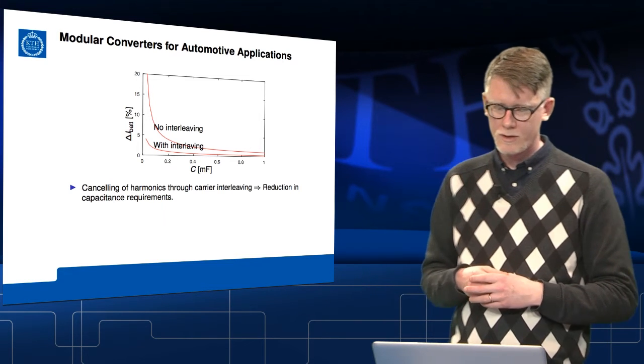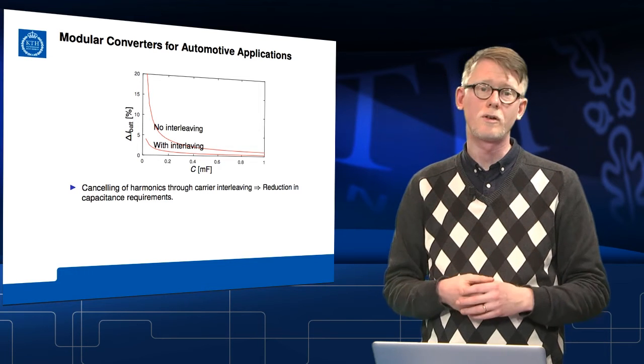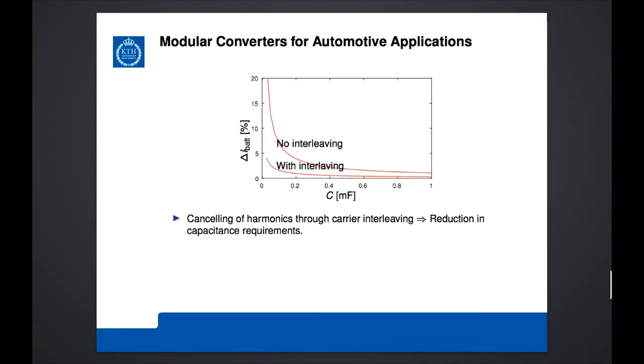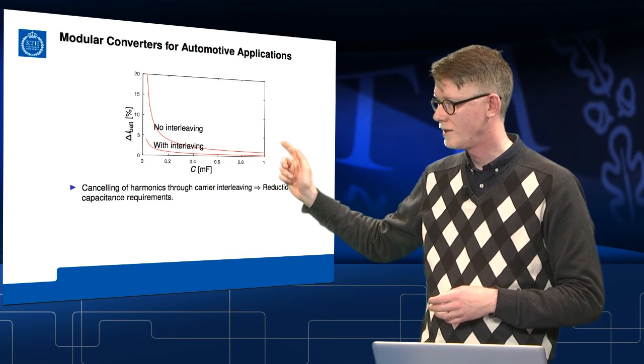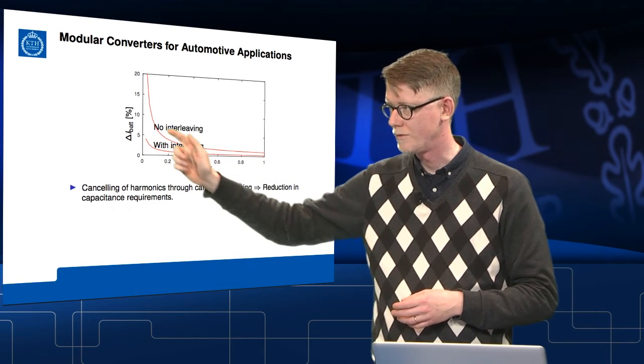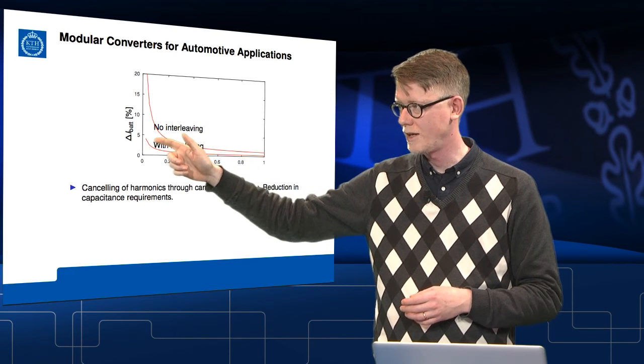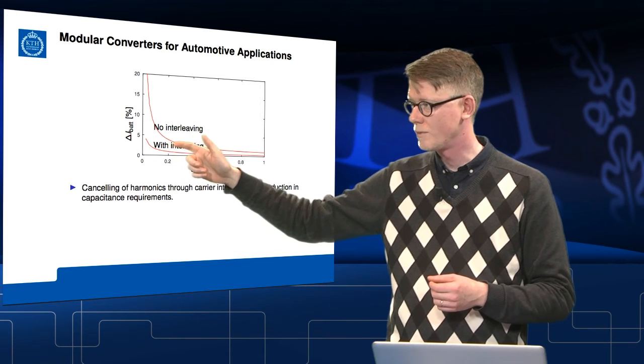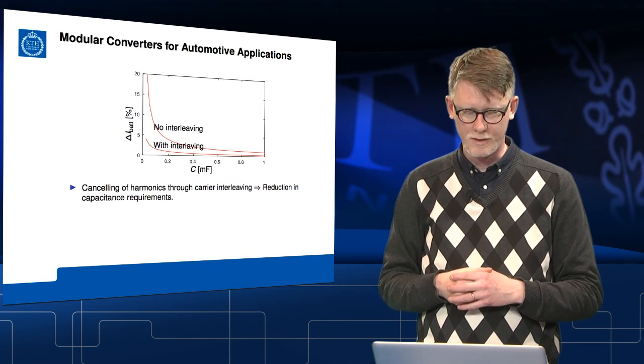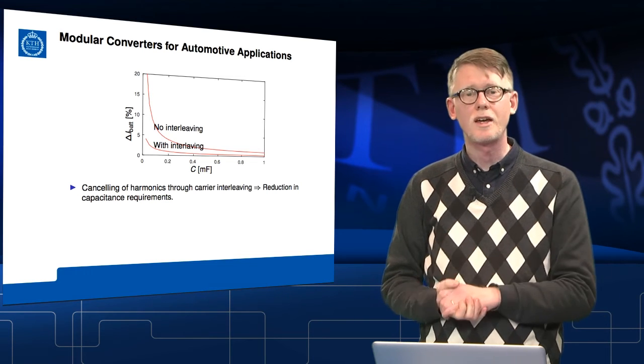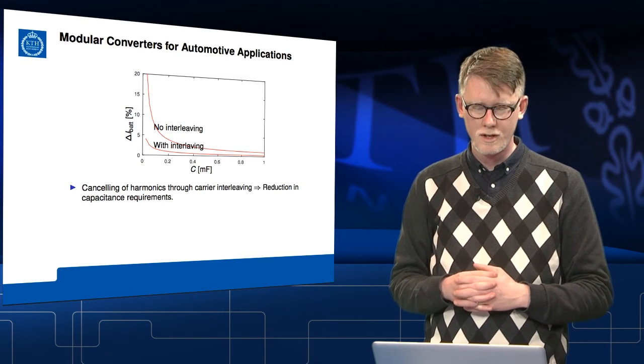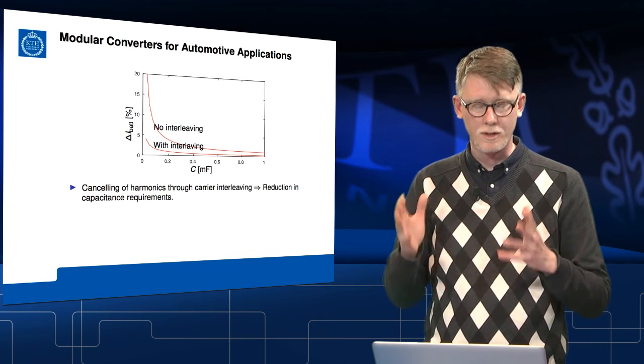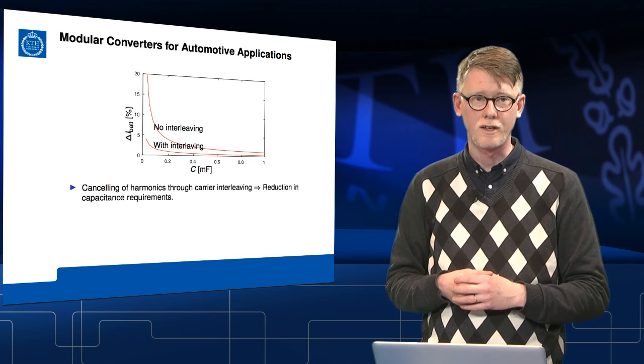In this figure, we have a converter comprising 4 series connected sub-modules and the resulting battery current ripple as a function of the required capacitance. Without interleaving, we get the red line above, and if we interleave the carriers properly, we get the red line below. For the same capacitance, we can reduce the battery current ripple substantially by carrying out this interleaving properly.